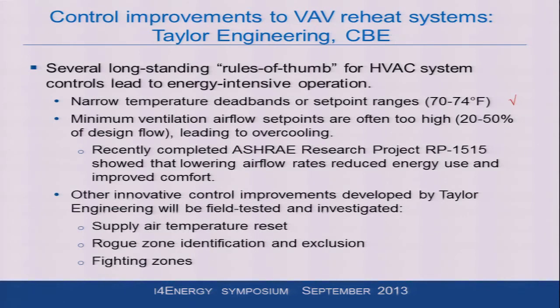So now we're going to just describe briefly this thing about the control improvements. So we've talked about the narrow temperature deadbands, which you can maybe offset with the personal comfort systems or even other things. Minimum ventilation airflow set points. These are also, by rule of thumb, set up so that the minimum airflows allowed out of VAV diffusers are often in the range of 50% of their maximum. They just throw away half of their throttling range because they feel that there may be poor air distribution coming out of the diffusers. Now, when you have these high flows and there might be low loads in the space, you end up with an excessive amount of airflow because your minimum has been artificially maintained very high.